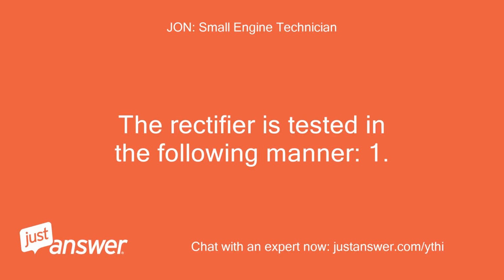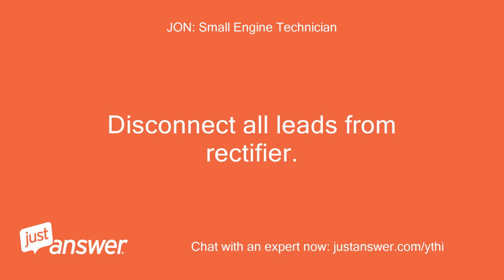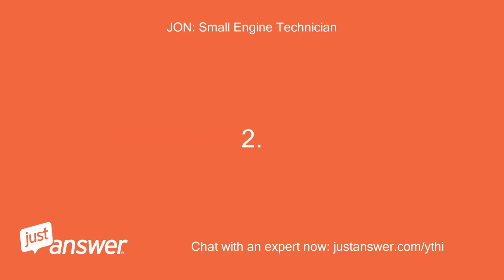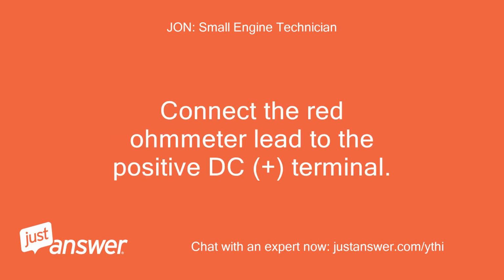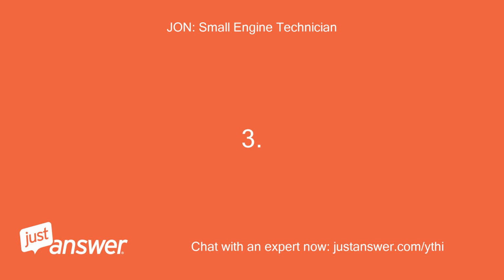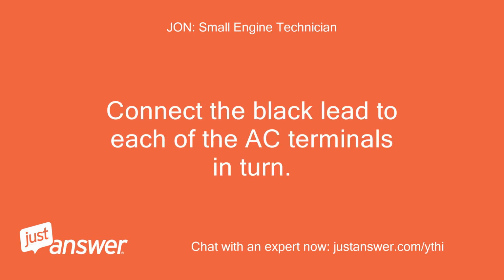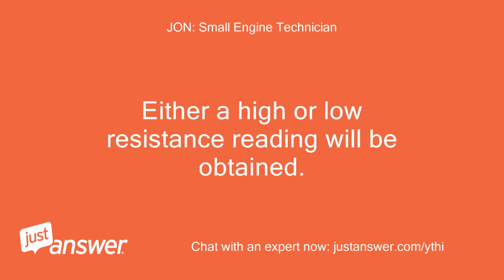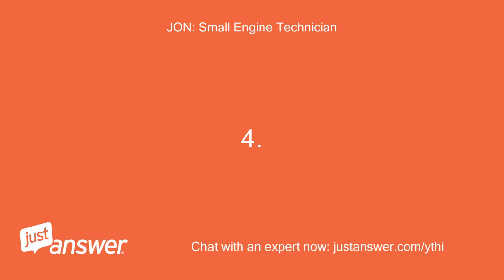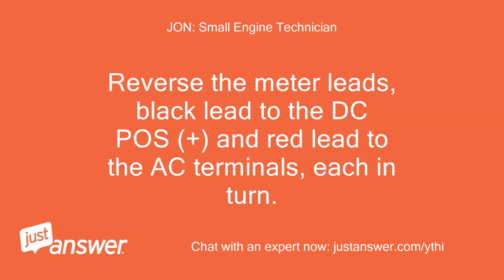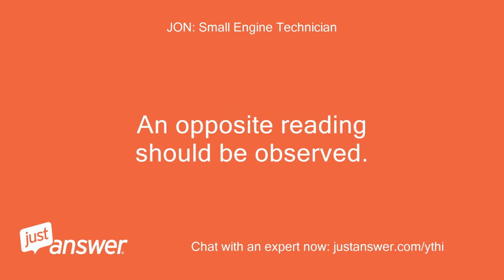The rectifier is tested in the following manner. 1. Disconnect all leads from rectifier. 2. Connect the red ohm meter lead to the positive DC, plus, terminal. 3. Connect the black lead to each of the AC terminals in turn. Either a high or low resistance reading will be obtained. 4. Reverse the meter leads, black lead to the DC POS, plus, and red lead to the AC terminals, each in turn. An opposite reading should be observed.